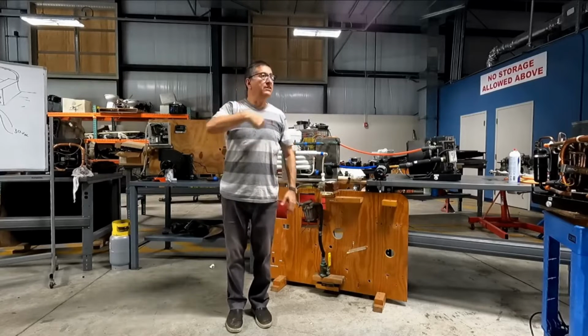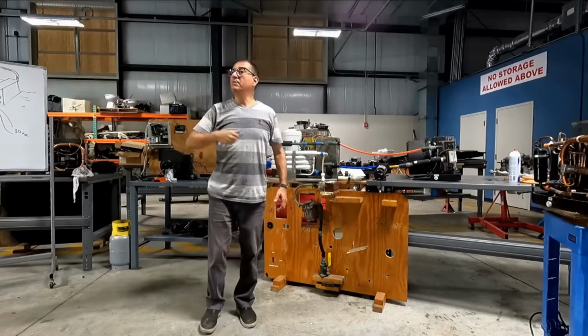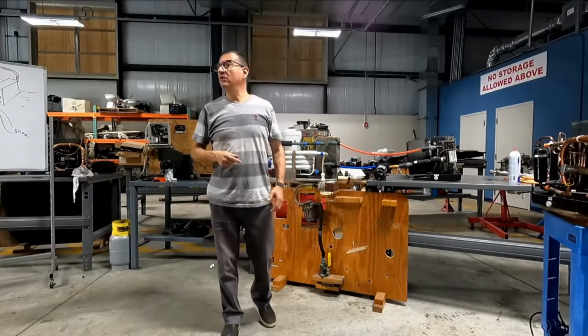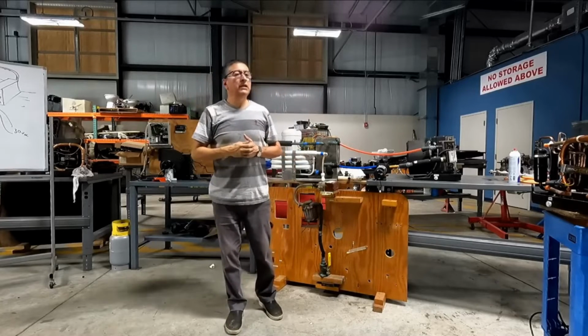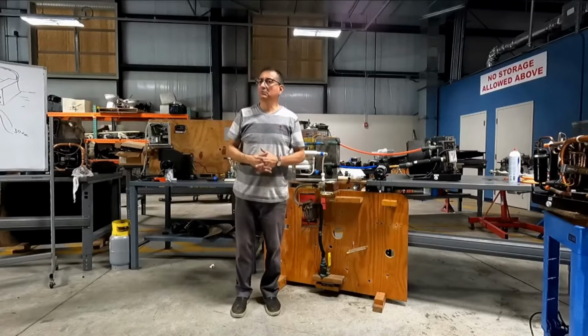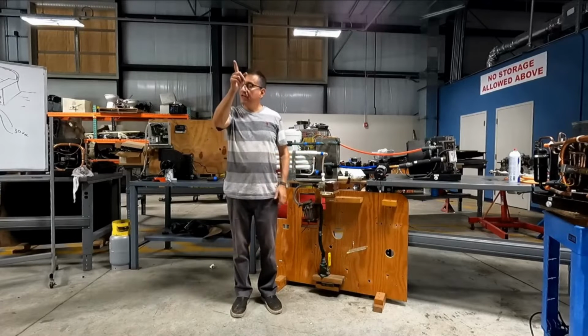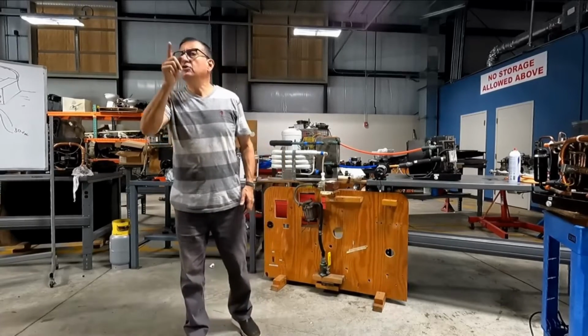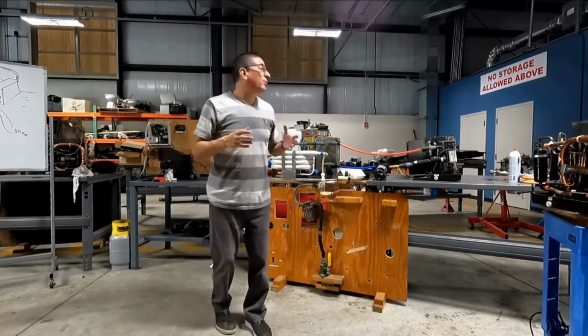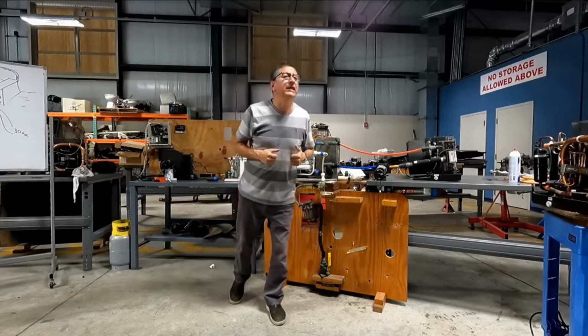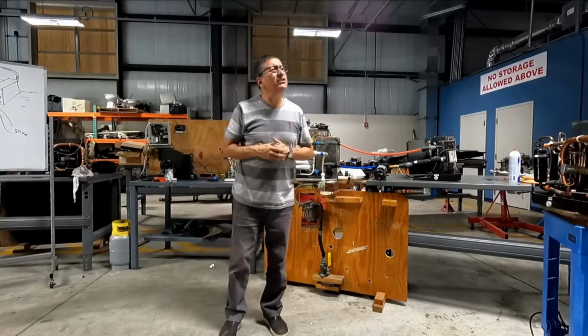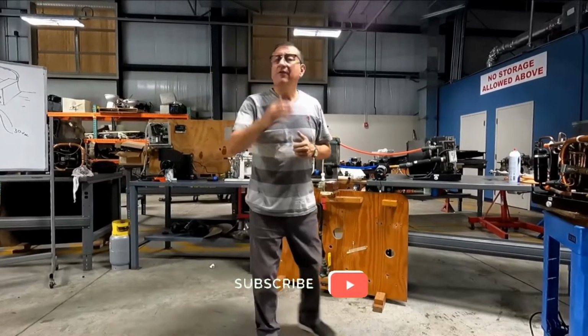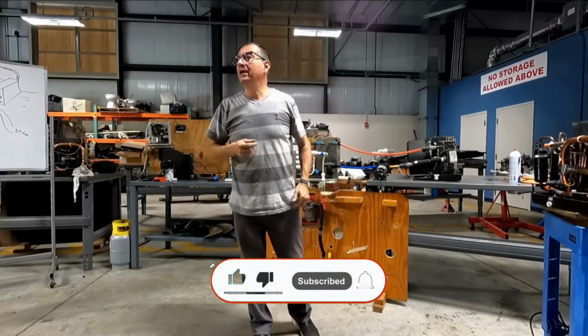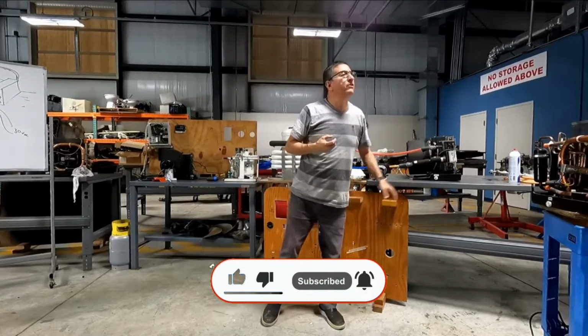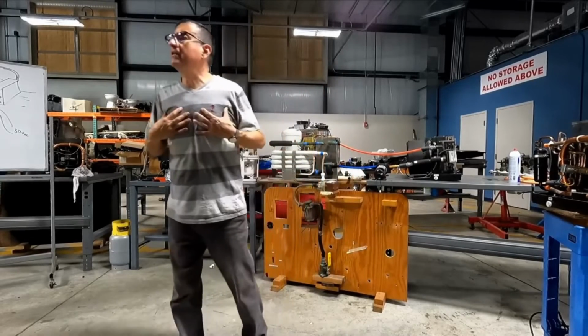The technician of the facilities of the university goes over there and calls the manager and says, yes, in the office of Mrs. Adriana, there is a lot of refrigerant on the ground. This is refrigerant? No. It's not refrigerant. It's coolant. Because the people, instead of using fresh water, prefer coolant. Engine coolant, motor coolant. Why coolant instead of fresh water? The freezing point is lower. And additionally, the additives in the coolant avoid corrosion in the pipes of the evaporator. For that reason, the coolant is better.